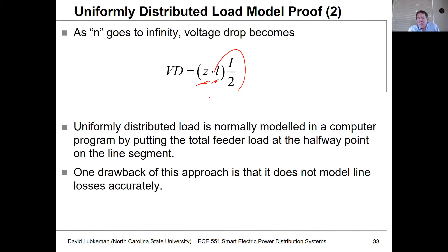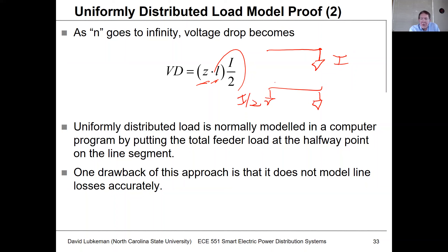Another way of thinking about this: for a uniformly distributed load, for the purpose of doing a voltage drop calculation, you can treat it as having half the load at the sending end and half at the receiving end. We'll see a number of work problems later in the course where we make use of this.